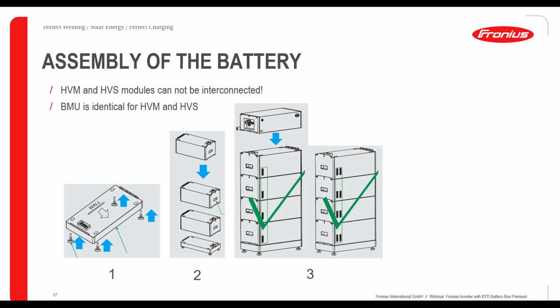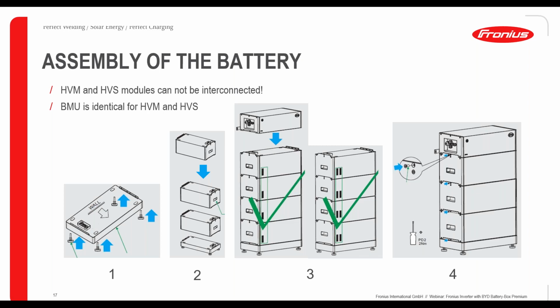A very important point here for installation is that you don't mix up HVM and HVS modules with each other. So if you're installing one battery tower, please make sure that you only use either HVM modules or HVS modules. These modules can't be interchanged, so please don't mix up HVM and HVS modules. On top of the last battery module, you are then fixing the BMU module. So there is this BMU module that you can see. And of course, again, you fix it with the screws on the side. And then the installation part of the BYD is done. After that, of course, on the upper part, you have this BMU and the connection area.